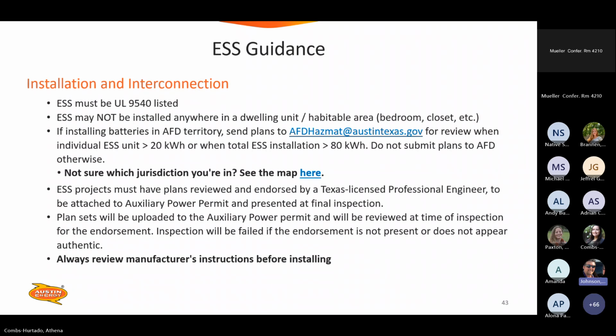If installing batteries in Austin Fire Department territory, send plans to afdhazmat@austintexas.gov for review when an individual ESS unit is greater than 20 kilowatt hours or when the total is over 80 kilowatt hours for a commercial installation, let's say. Don't submit the plans to AFD otherwise, though. And if you're not sure what jurisdiction you're in, if you're in the ETJ or if you may or may not be within Austin Energy territory, we do have a map at that link right there that will tell you where Austin territory ends, but ETJ continues with Austin Energy territory until it gets into other utilities. Encore, Bluebonnet, PEC are the ones that are most local around us.